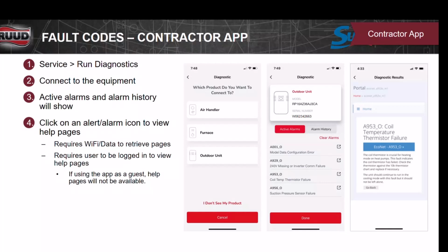We also have one for a missing inverter communication failure. We might not have 240 to the inverter. If you have 24 volts to the inverter, the lights are going to be on, but you don't have high voltage to it. Or vice versa, you could have high voltage to it and no low voltage to it. So always check your fuses, because usually it's a blown fuse.